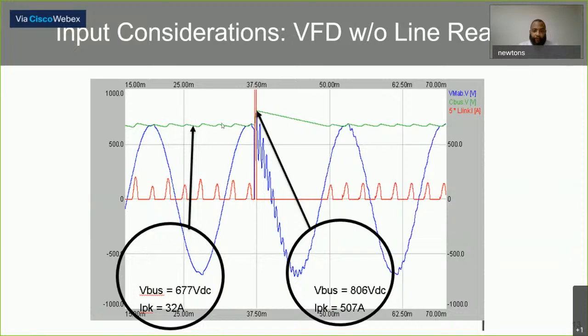This green line, this green trend, is going to show your DC bus on your VFD. So in this case, it's floating. Typically, it floats around 650 volts, 678 volts. And they got it marked down below where it says V bus. Your blue line is going to be your AC input line connections or your line voltage. And then your red line is going to be your AC input current.